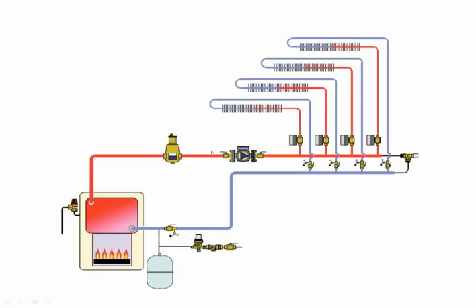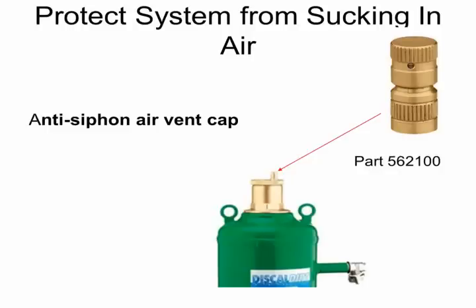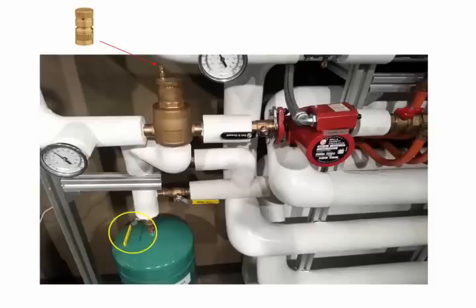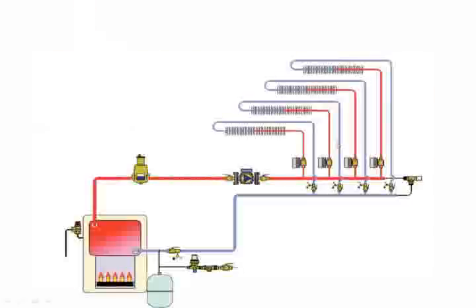So always pump away from an expansion tank. Or we could put it down here because there's very little difference in pressure drop between here and where we had it before. Now what if we waterlog the expansion tank? Well, it's basically similar to not having an expansion tank at all, right? And we could have air come into our air separators. So Caleffi offers an anti-siphon air vent cap to protect against this actually happening. Here's our mechanical room, actually right here in Milwaukee, where you can see our little protection cap. Under pressure, it vents out air. Under a vacuum, it prevents air from being sucked in. So even if you forgot to open your isolation valve on your expansion tank, it protects this Bell and Gossett pump from airlocking, keeping it working effectively.